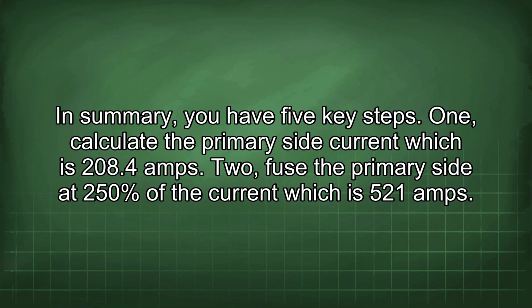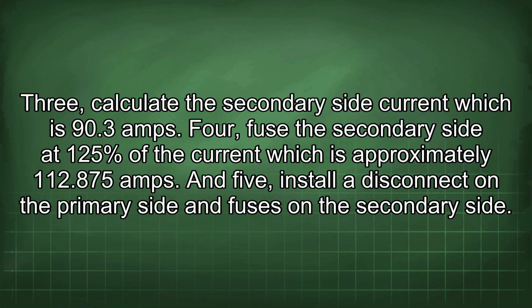1. Calculate the primary side current, which is 208.4 amps. 2. Fuse the primary side at 250% of the current, which is 521 amps. 3. Calculate the secondary side current, which is 90.3 amps. 4. Fuse the secondary side at 125% of the current, which is approximately 112.875 amps. And 5. Install a disconnect on the primary side and fuses on the secondary side.